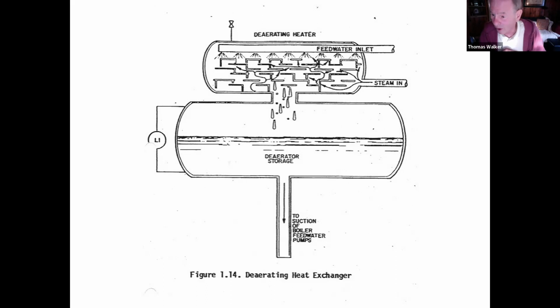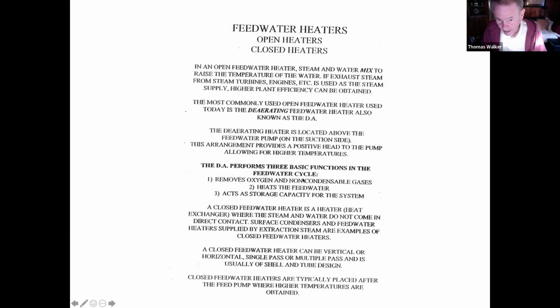They've always got water available at the suction. Isn't this DA a wonderful thing? Now, on the test, they're going to ask you, what 3 things does a DA do? It removes oxygen and non-condensable gases. It heats the feed water, and it adds storage capacity for the system.